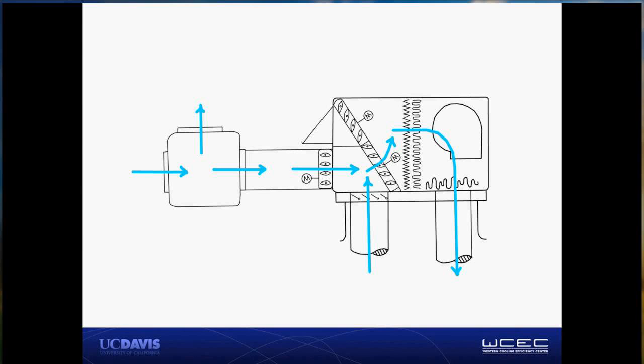But it's important to note that the pressure on the outlet of these indirect evaporative systems needs to be maintained positive and within a particular range. That's very important for folks to realize. We've seen a variety of different customers and applications where they've tried to add the indirect evaporative coolers onto rooftop package units, but haven't made the provisions to keep that at a positive pressure, and the system may still work, but the performance will definitely suffer.